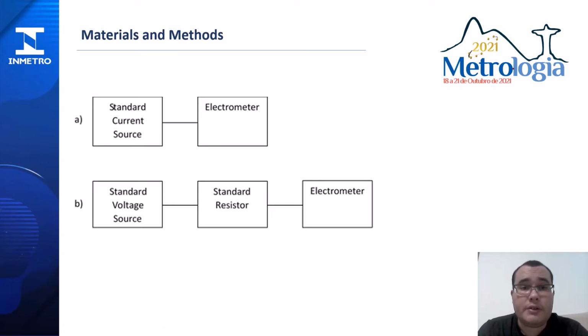To validate the system using the Ohm's law method, it was necessary to compare the values obtained with the developed system with the values obtained with the current laboratory system. This comparison was performed by calibrating the 20 microamperes range of an electrometer using both methods. The current method used in the laboratory is the method of comparison with a standard current source. The implemented method is the Ohm's law method. We use a multifunction calibrator as a standard current or voltage generator, depending on which method is in use. A set of standard resistors was used, and all measurements were made in a Faraday cage.